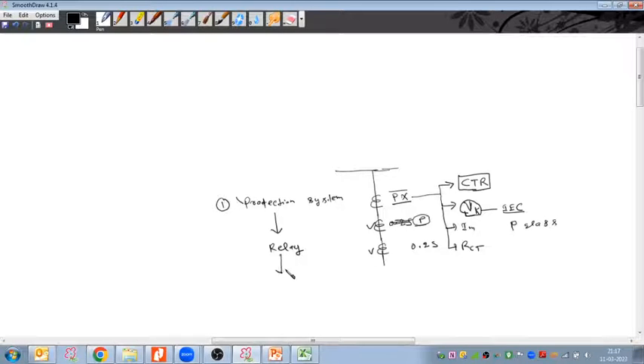Once the relay selection is done, and you know what make of relay you are going to use based on the protection system, then you download the relay application manual. There are many manuals for the relay, like the technical manual also available. So do not download the technical manual. In the technical manual you will not find any CT requirement formula. For the CT requirement, the manual name is the application manual. So download the application manual, and there would be 600 or 700 pages in it.